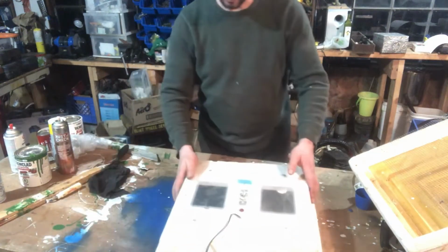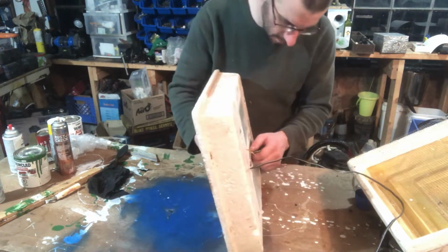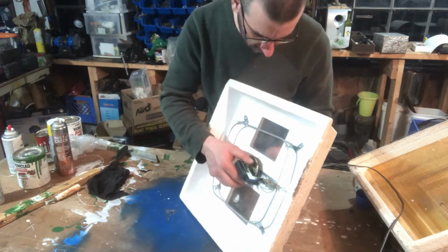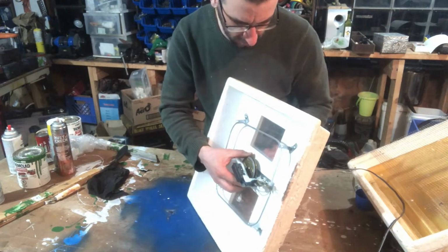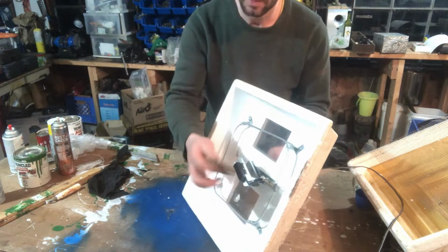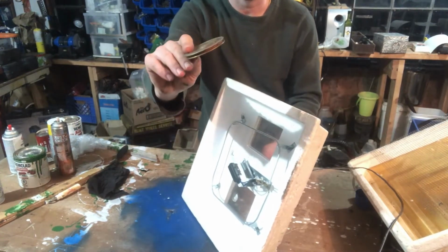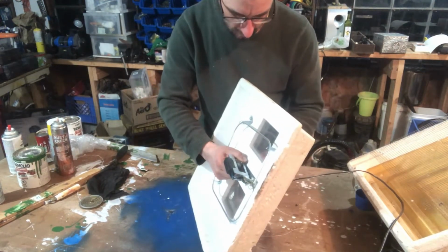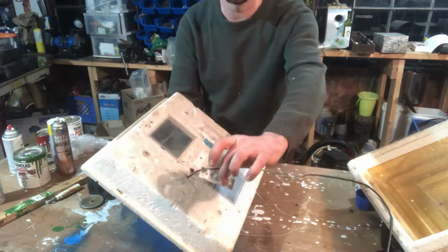The top part, see how it's put together. There's 4 screws that hold the element itself in place. The wafer just unscrews, and I think that just all comes apart when you unscrew the wafer. So there's the wafer. This thing, when you set the temperature, I think it expands or contracts slightly, and that's how it turns it on. Okay, this part unscrews here. So there, that comes off the top.